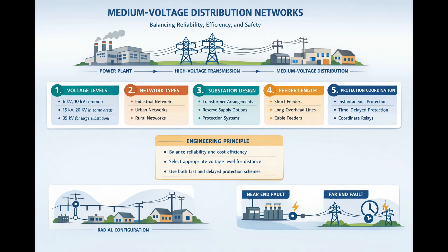Medium voltage networks form the link between high voltage transmission and low voltage consumers. At the top level, we have the 110 kV transmission networks. This is the regional backbone. From there, power flows into primary substations. In those substations, voltage is transformed from 110 kV down to 35 kV and 20 kV, 15, 10 kV or 6 kV, depending on the regional standards.